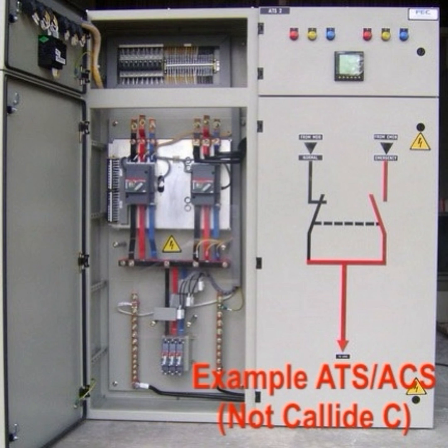Again, presumably, had they been replaced, they would have been replaced with a like-for-like, and flooded cells have been out of style for various reasons for decades, so AGM lead acids are the most likely option. Having said that, AGM battery manufacturers can prohibit parallel connection and threaten invalidation of warranty if it's ever done, so maybe that was a factor too. There's simply not enough information provided to be certain either way.